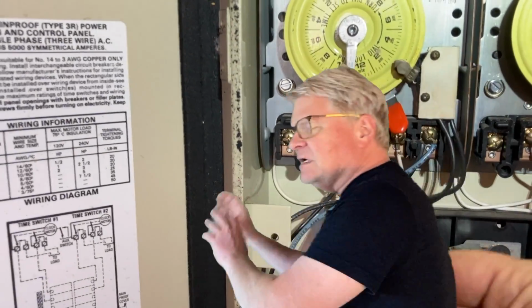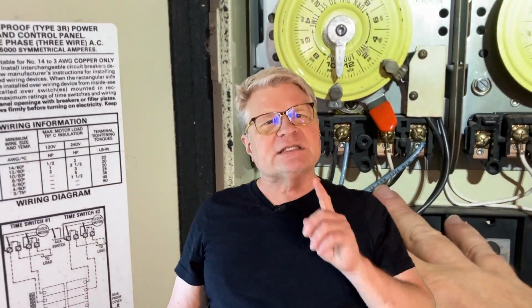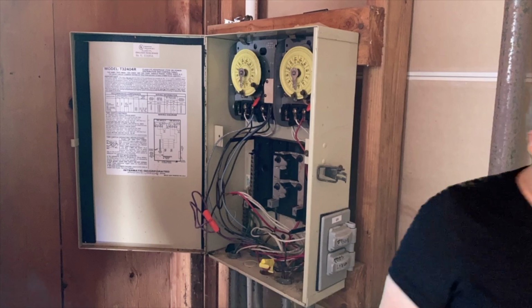Hold on, I'm about to say something that's not totally wrong but isn't right either, so let me fix that. What that aux switch really is, is a fireman switch, used on older heaters like this one to turn the heater off about 20 minutes before the pump stops so everything in the boiler can cool down, which helps with pipe knock and whatnot. A modern heater does it with electronics, and I'll show you that wiring a little later in this video. Okay, you can continue.